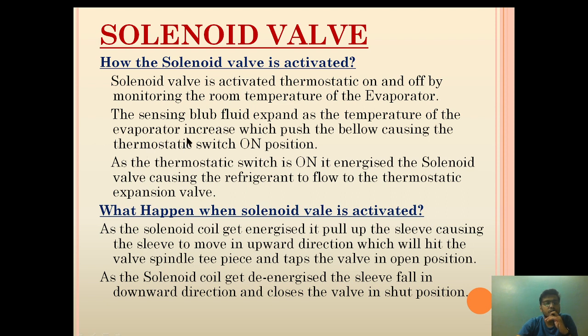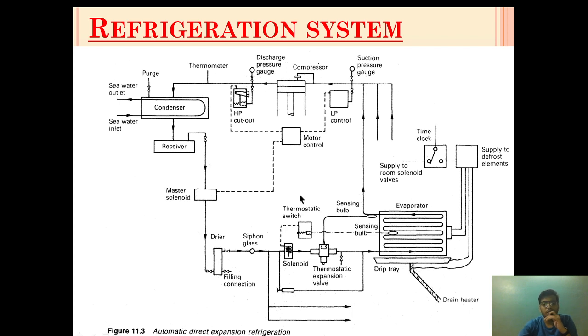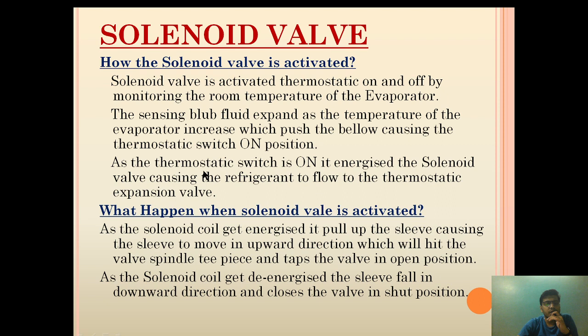When the temperature of the evaporator increases, the sensing bulb fluid expands, turning from liquid into gaseous form and exerting pressure on the bellow, causing the thermostatic switch to move to the on position. As it moves to the on position, the solenoid valve is energized and allows the flow of refrigerant to the thermostatic expansion valve.